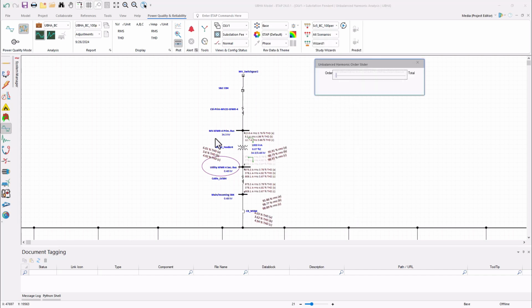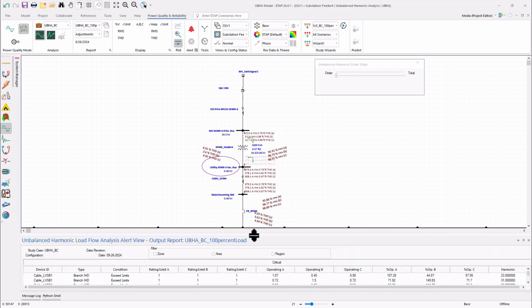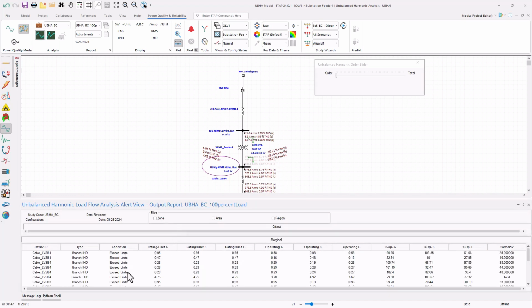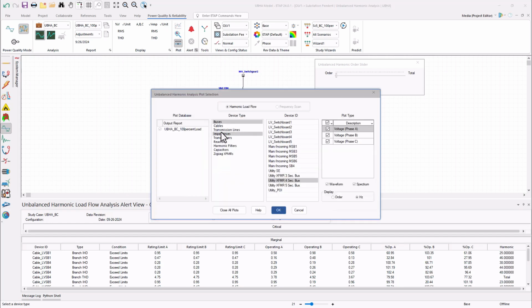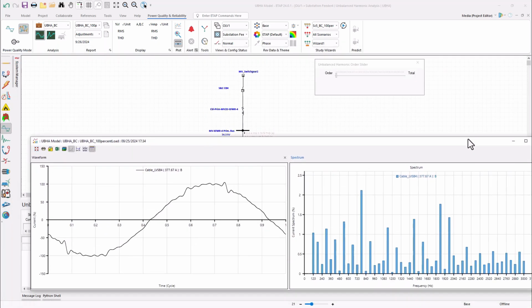Let's look at the voltage distortion results at this bus and the current distortion results at this branch service entrance cable. Let's go to alert view. If you notice, we have several alerts for cable LVSB4 for different harmonic orders, including the one for total harmonic distortion, showing limits of 4.75% for current distortion, whereas phase B has 4.92%, it's exceeding the limits provided in the standard and study case settings. So let's plot this to see how distorted the waveform is. Cable LVSB4 phase B. So it's a distorted waveform.